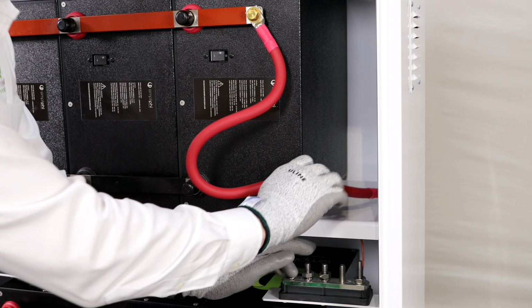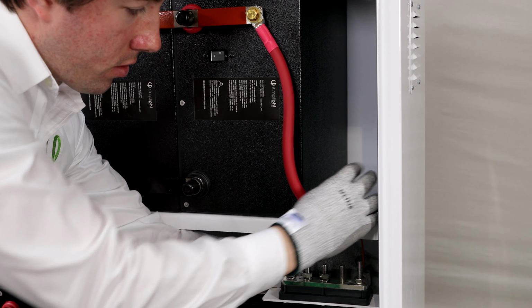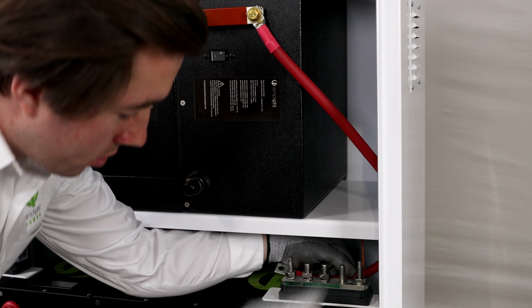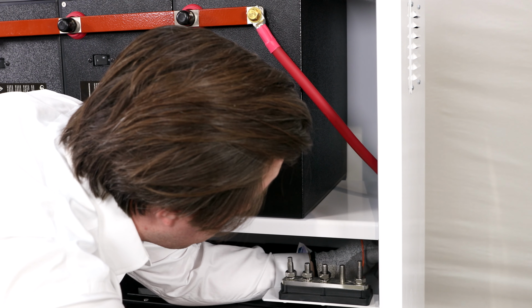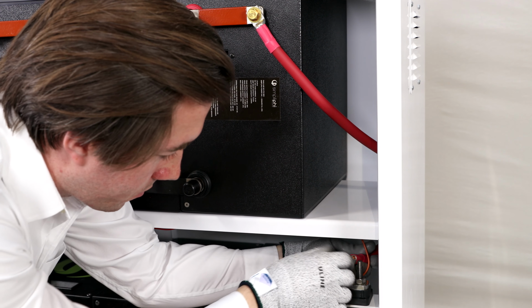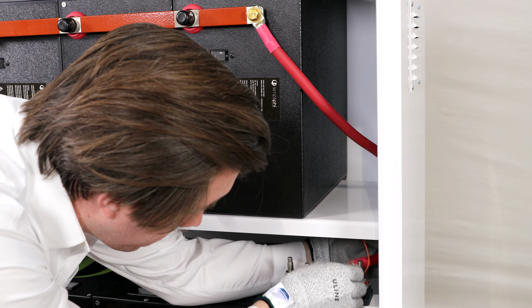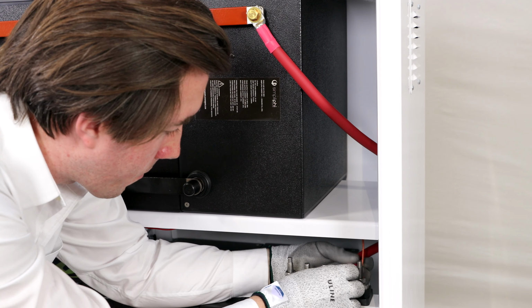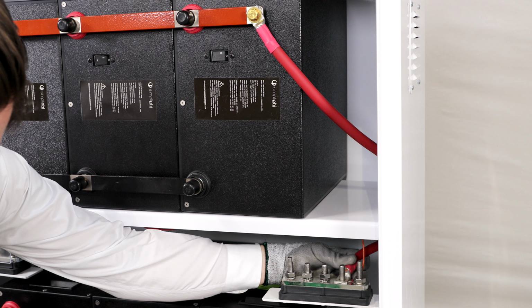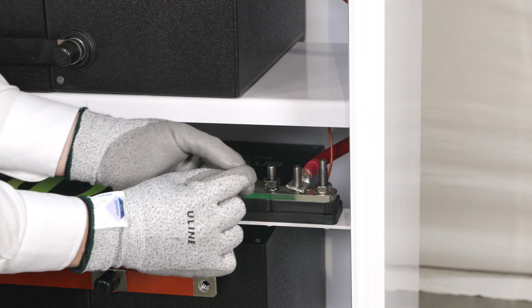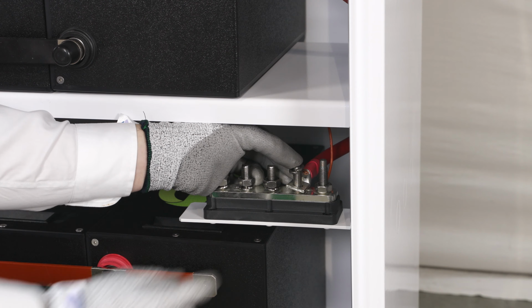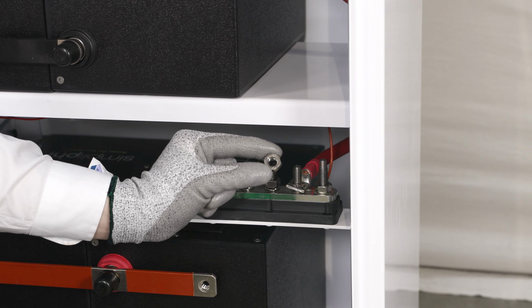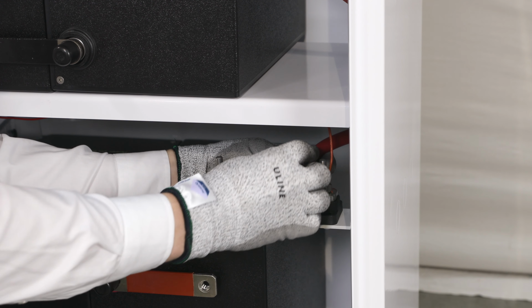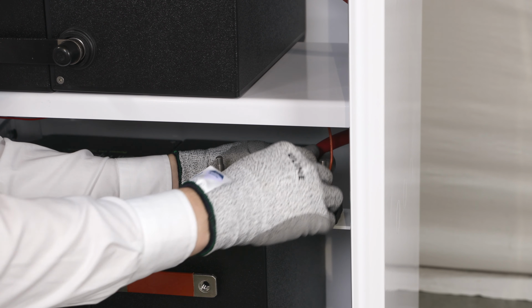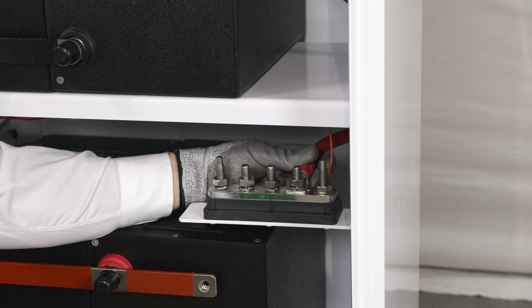Route the cable from the bus bar to the 5-point terminal block through the small gap between the shelf and sidewall. When routing the cabling, be careful not to damage the small wire that is already attached to the 5-point terminal block. This wire routes from the terminal block to the venting fan. Attach the cable's lug to the 5-point terminal block, followed by the lock washer and nut that were removed earlier. Firmly tighten the nut to secure the cabling lug to the 5-point terminal block.